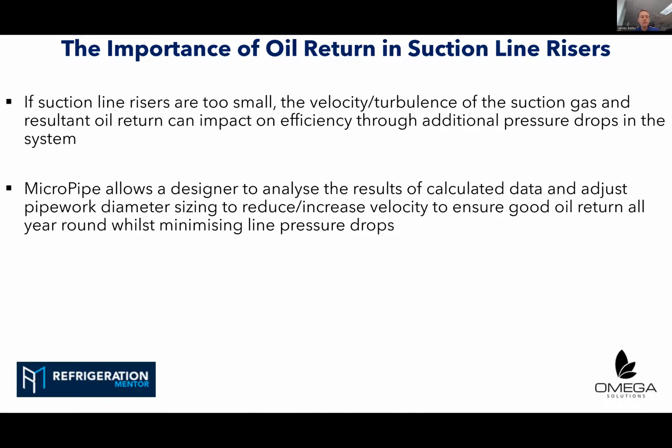So this is quite important, because as a designer, what I've always been taught, working in SI metric units, is when I do a MicroPipe calculation, the input is the lowest temperature that corresponds with the evaporating temperature of the display case. Ultimately, we know that the saturated suction temperature when we get to the compressor is 2 degrees lower. So we allow 2 Kelvin line loss from the point of evaporation all the way through.